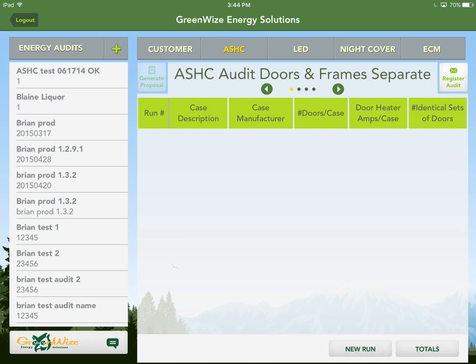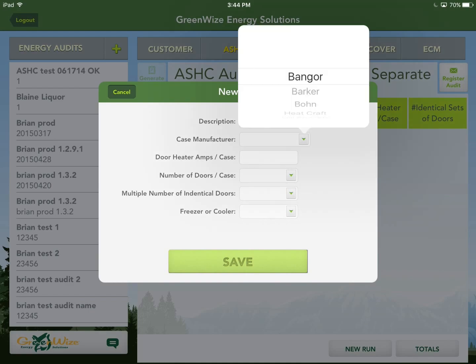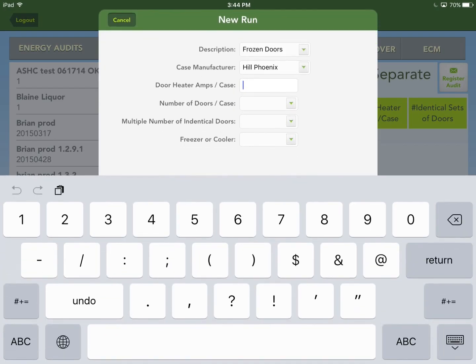Enter a run description — something like 'frozen doors.' Enter the case manufacturer if known. For door heater amps per case, this can be found on the manufacturer's tag or measured with a multimeter. If neither option is available, the general rule of thumb is: coolers are 3/4 amp per door, and freezers are 1.5 amps — basically double. For this example, two-door freezer cases at 1.5 amps per door gives 3 amps per case, so the total amps is 3 times 2.